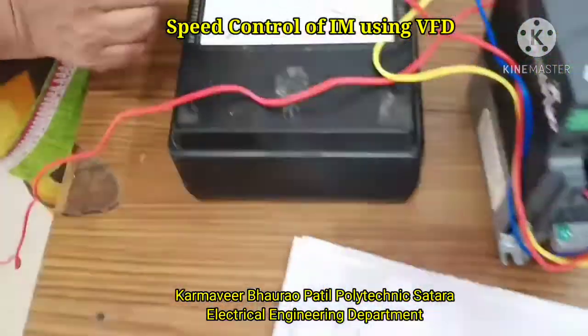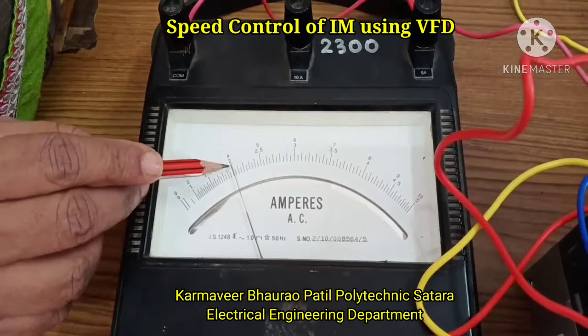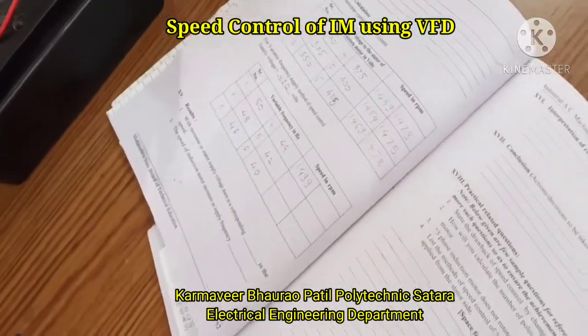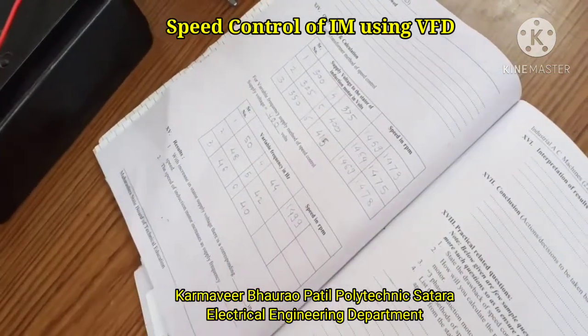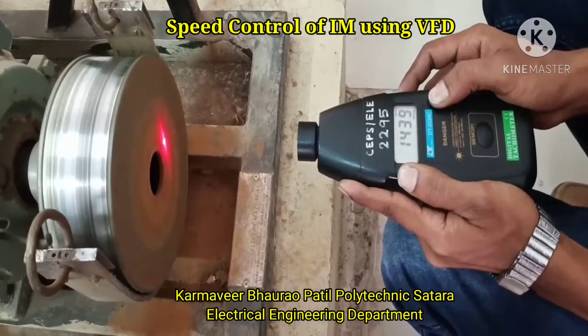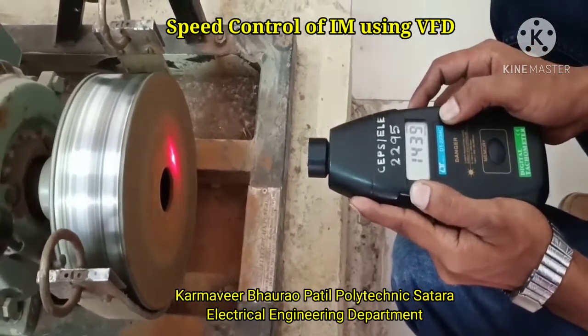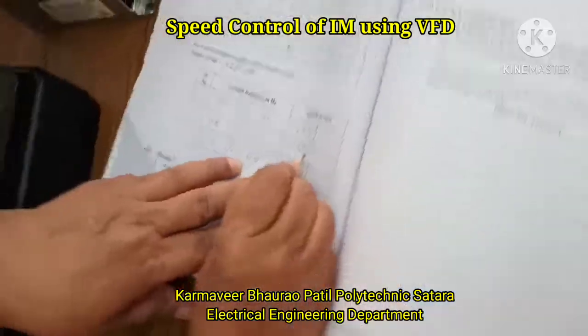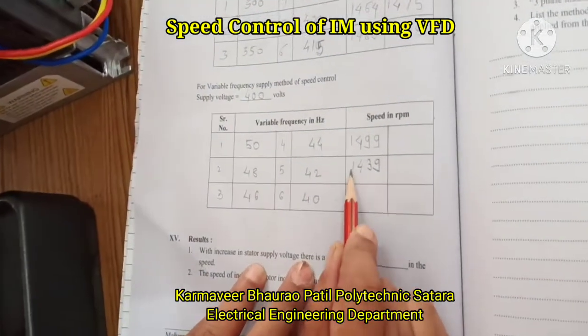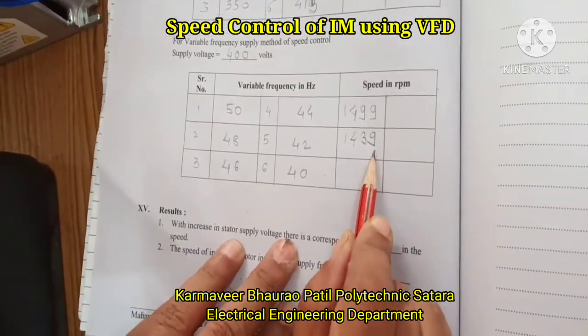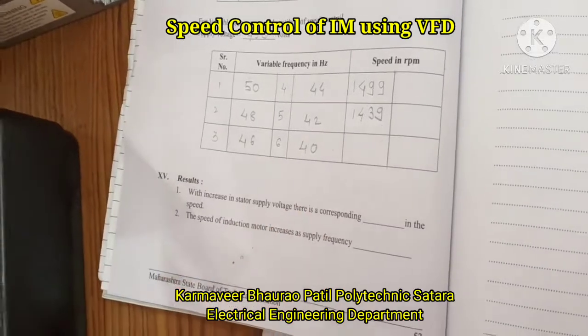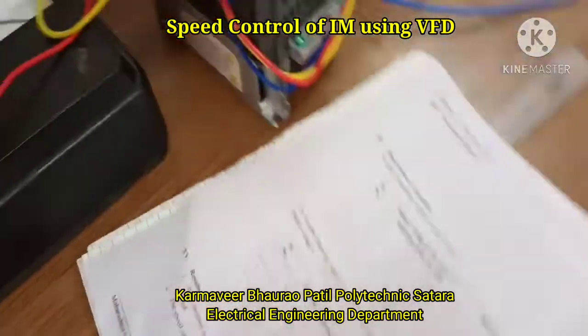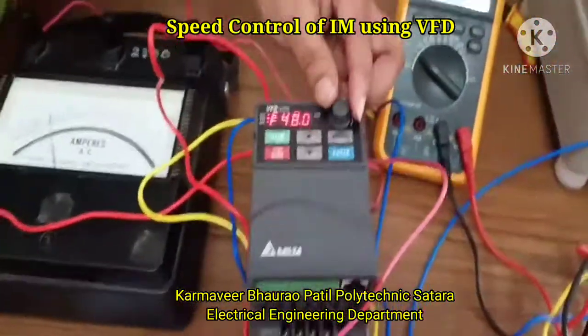Frequency I adjusted at 48. Current you will see it is about 2.1 ampere. But we are not required to note down the current. Just to watch the current, we have connected the ammeter. So the second frequency is 48 Hertz. So speed is 1439. I have written the second speed as 1439. And now how much is the frequency? 46 Hertz. So let us decrease again the frequency.